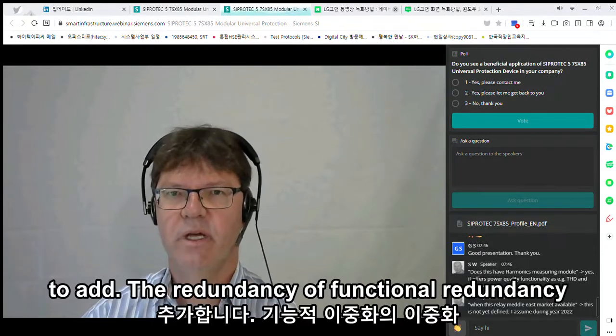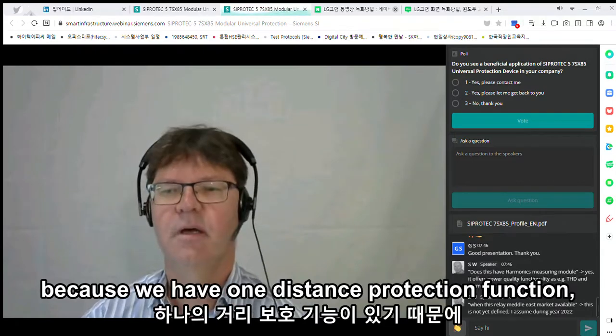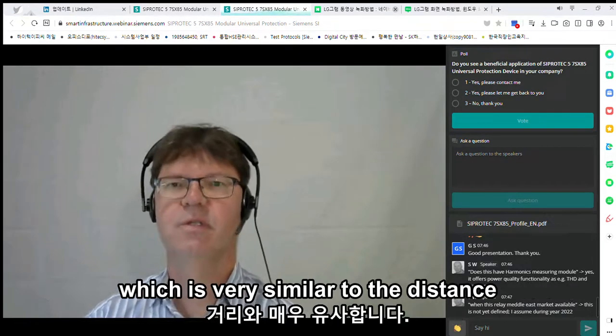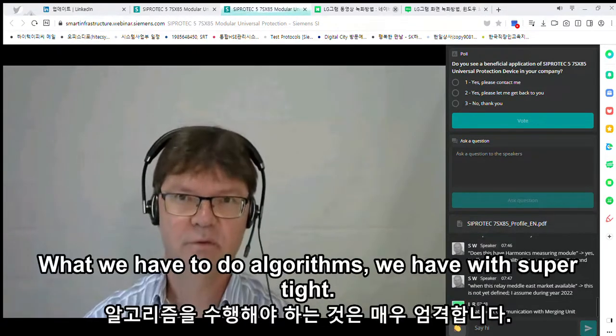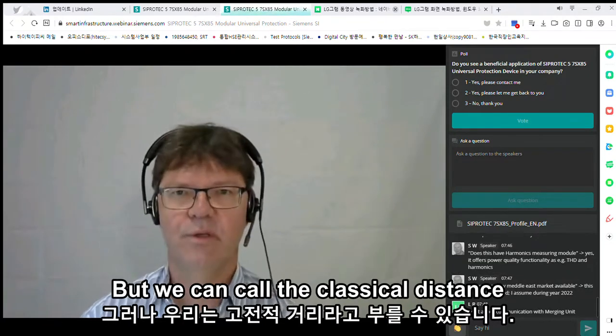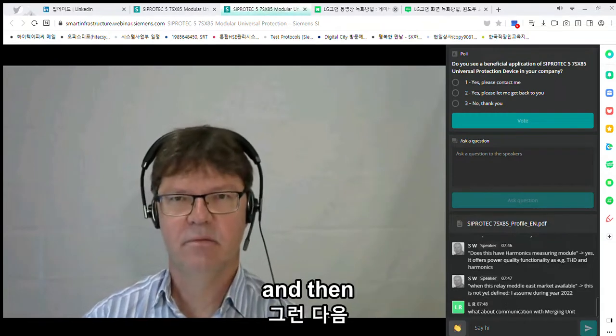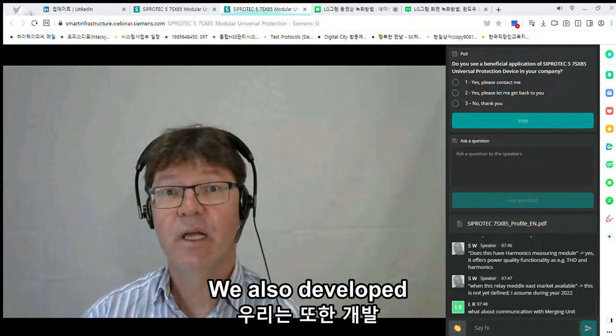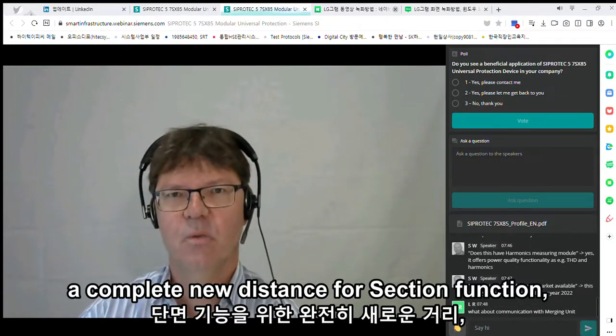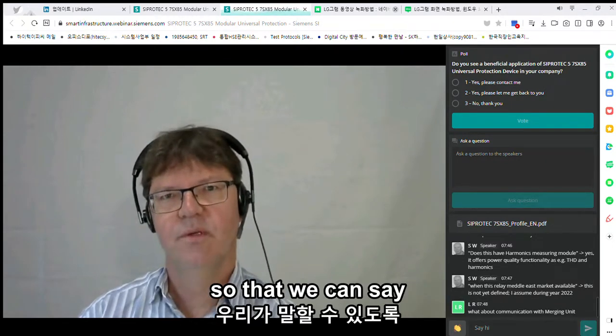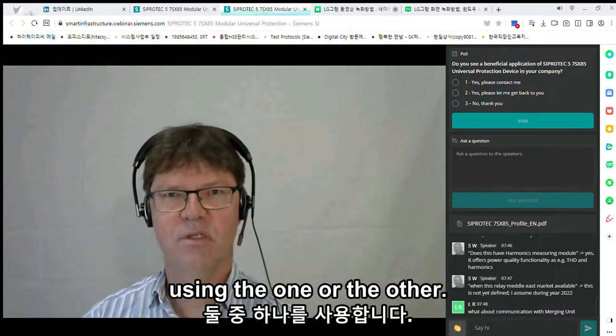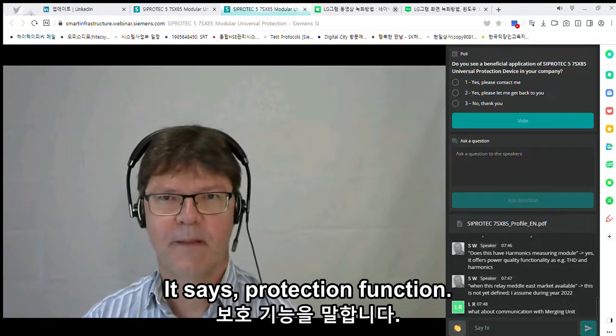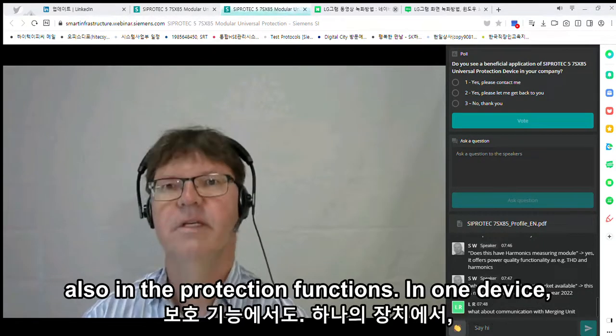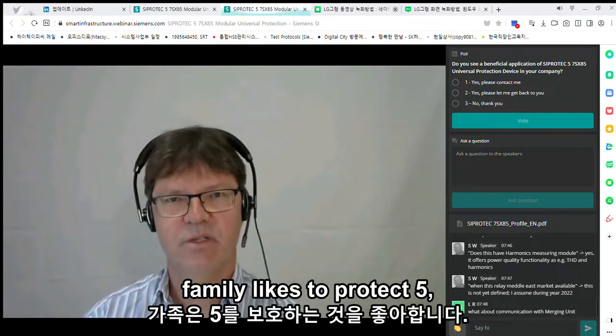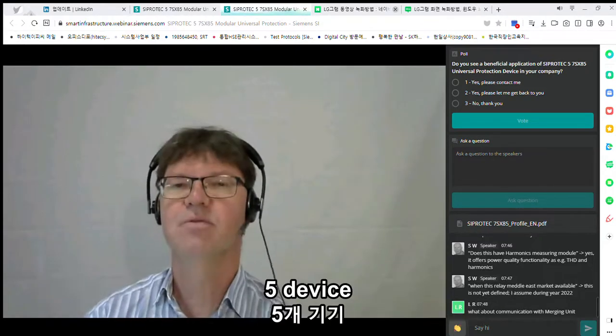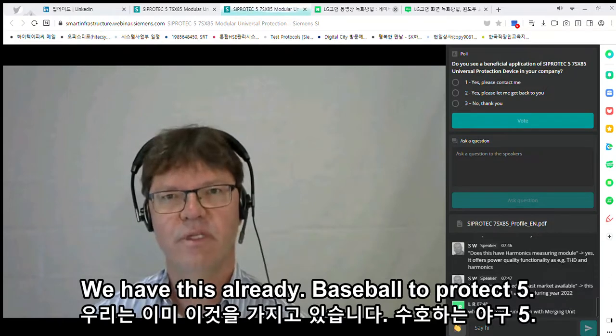Here we also have the possibility to add software redundancy or functional redundancy, because we have one distance protection function which is very similar to the approach and the algorithms we have with SIPROTEC 4, what we can call the classical distance protection function. And then during the development of the SIPROTEC 5 relays, we also developed a completely new distance protection function, which is based on other principles, so that we can say we have also a functional redundancy using the one or the other distance protection function. And this is one example of having redundancy also in the protection functions in one device family like SIPROTEC 5. So there is no need to have a SIPROTEC 4 and a SIPROTEC 5 device to have a functional or software redundancy. We have this already based on SIPROTEC 5.